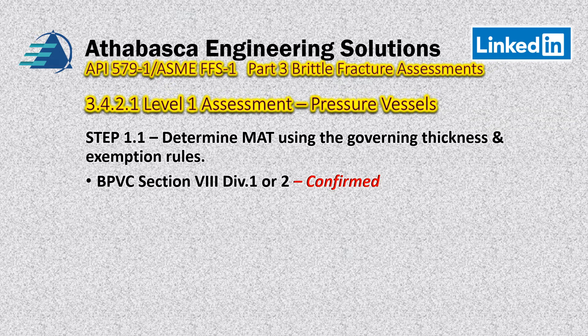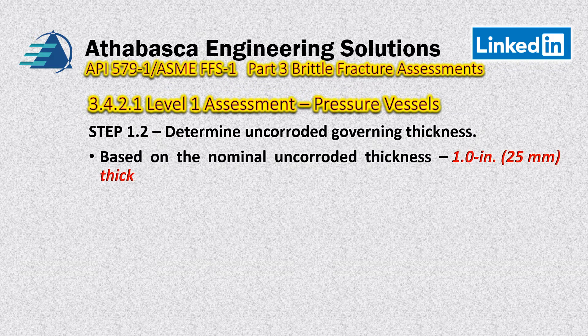Continuing, we have to review some exemption rules. Level one is valid only for boiler pressure vessel code Section Eight Division One and Two, and we've just confirmed that. The design allowable stress must be less than 25 KSI or 172.5 megapascals, and we've confirmed that based upon the allowable stress for SA 516 Grade 70N. Now we'll continue looking at step 1.2 — determine the uncorroded governing thickness. For shell, it's relatively simple: it's based upon the nominal uncorroded thickness of the plate. For shells, we just look at the nominal thickness. These rules are consistent across the boiler pressure vessel code as well. So in this case, we're at 1.0 inches.